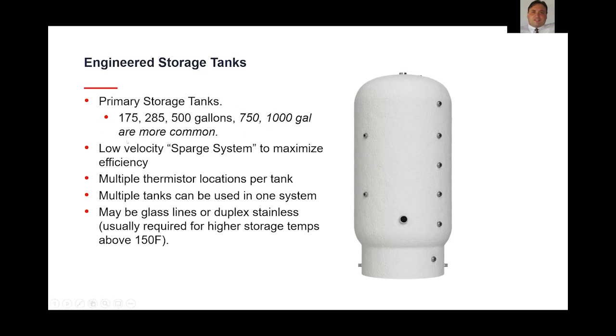So these are some common sizes that you'll see available. This is more indicative of Mitsubishi's offering. Tank sizes, starting at 175 gallons up to 500 gallons. And then we're also looking at tank sizes up to 1,000 gallons as well. But these tanks are specifically designed for these series applications. They contain sparge fittings to minimize velocity and velocity jets inside of those tanks that really promote mixing, which is not advantageous. We want to maintain stratification in the tanks. Again, they're going to have multiple thermistor locations. Again, that ties into the control side of these heat pumps in terms of triggering the heat pumps on and off. You may see these with glass lined or duplex stainless requirements. That usually comes into play when you're dealing with hotter storage water temperatures well above 150.